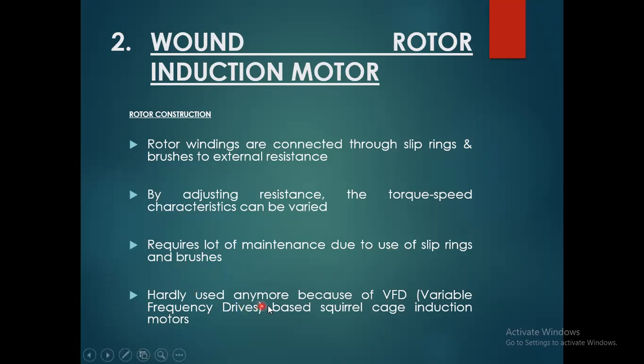They are hardly used by anyone anymore because of VFDs, variable frequency drive based squirrel cage induction motors. If we want to use a variable speed motor drive, we prefer a VFD, a variable speed drive, to control the squirrel cage induction motor. So this is the main trend now: using the squirrel cage induction motor with a VFD as the driving mechanism.